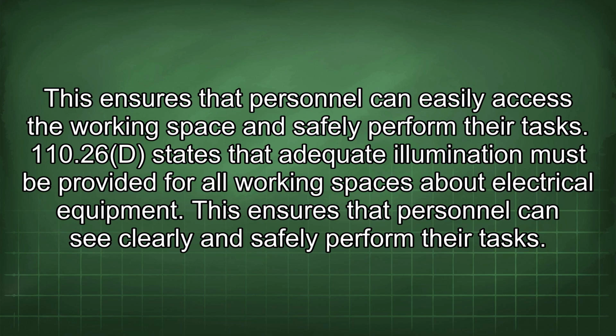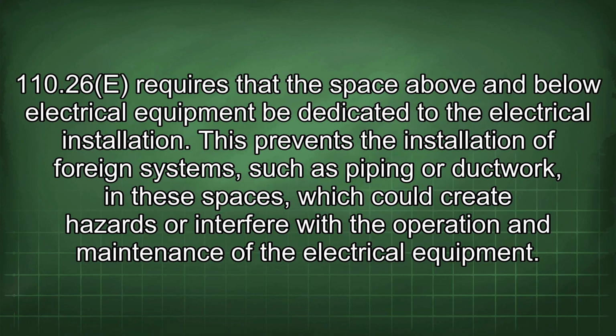110.26d states that adequate illumination must be provided for all working spaces about electrical equipment. This ensures that personnel can see clearly and safely perform their tasks. 110.26e requires that the space above and below electrical equipment be dedicated to the electrical installation. This prevents the installation of foreign systems, such as piping or ductwork, in these spaces, which could create hazards or interfere with the operation and maintenance of the electrical equipment.